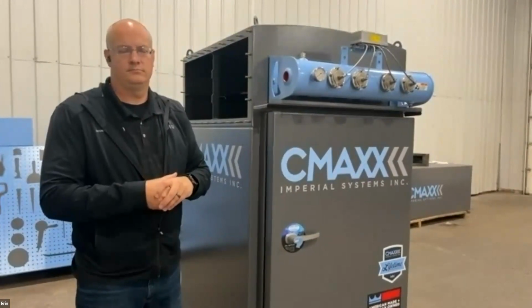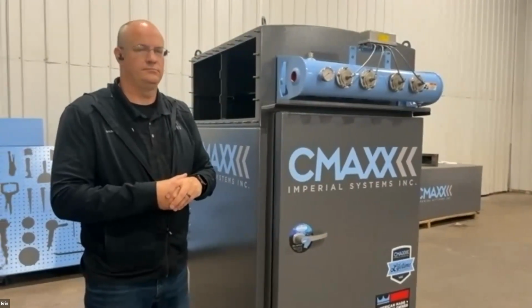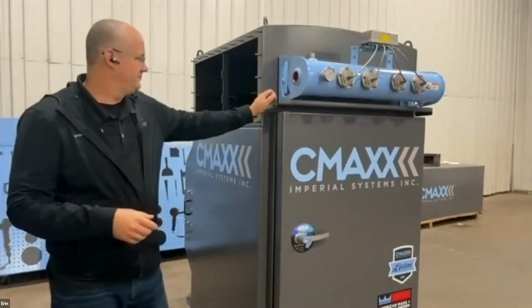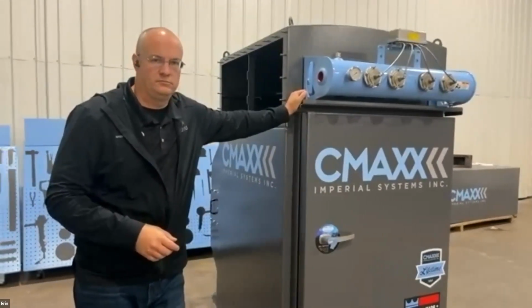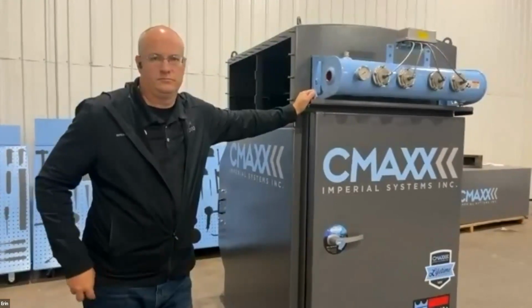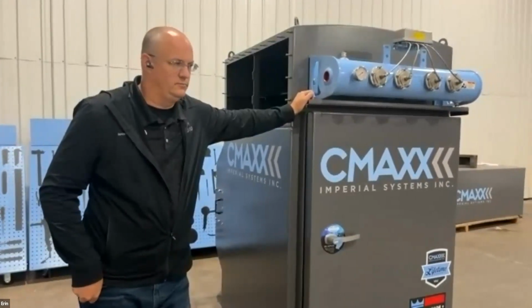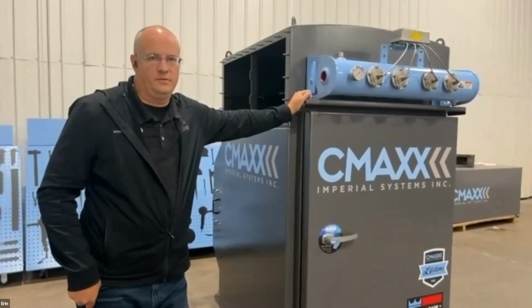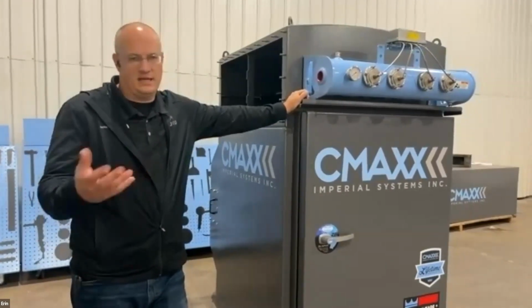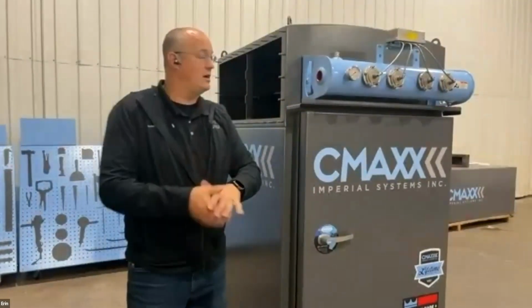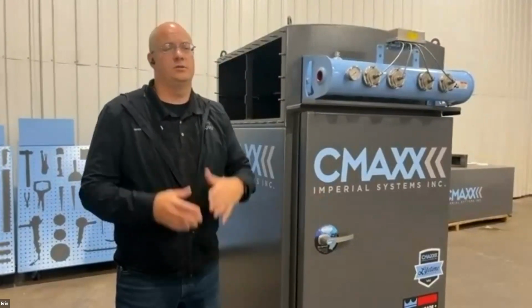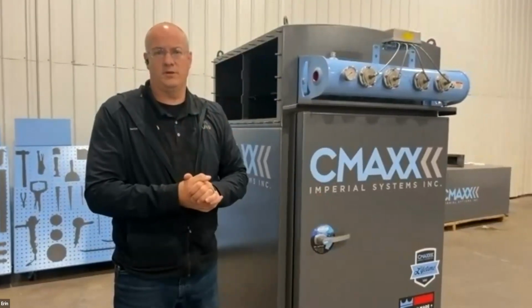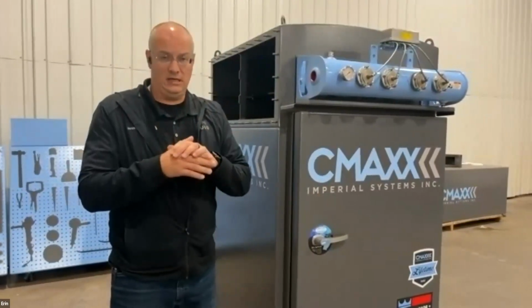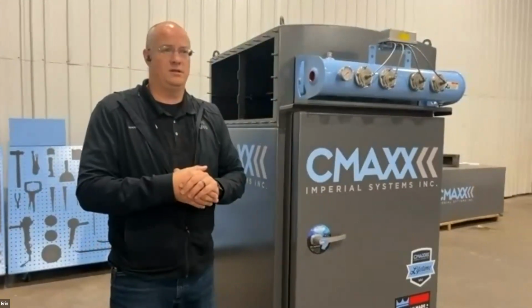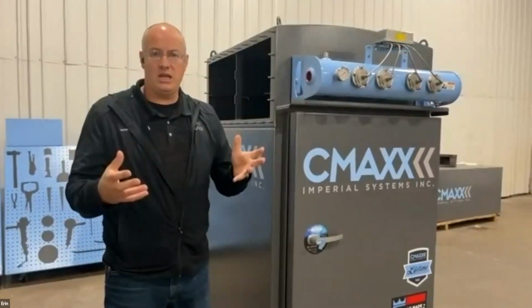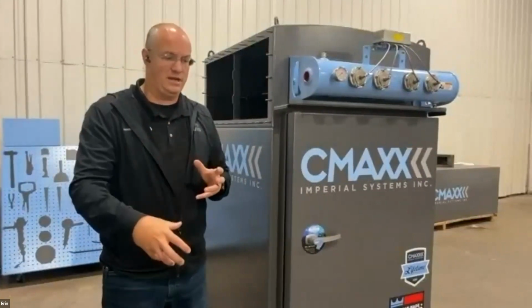So when we talked about the differential pressure between your dirty air side and your clean air side, the ports are on the side. Those tubes come back to the control panel, and that is what activates or controls when that on-demand pulsing takes place for the filters. Exactly. That's how this style of collector works. Dave talked about touching on some other styles earlier. There are some that just clean all the time, some that clean by shaking, and some that clean by just blowing air down in.